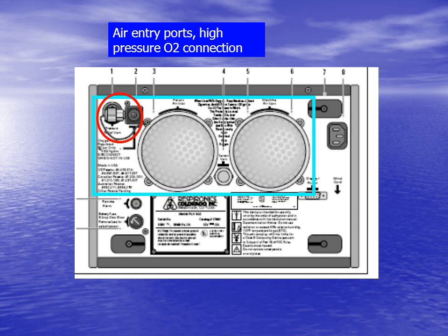This model of PLV does have the option of delivering high-pressure O2 to the patient via connection in the back. But due to the high cost of running high-pressure O2 through this vent in the home care setting, it is rare to find the vent set up in this way. O2 is usually bled in. If the high-pressure hose is used, however, percentages up to 90% of O2 can be accurately delivered.